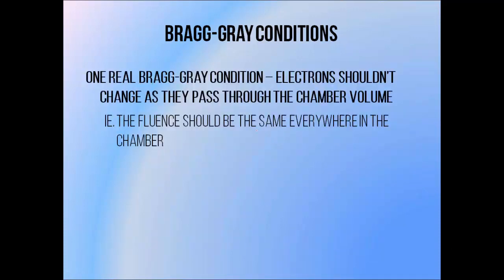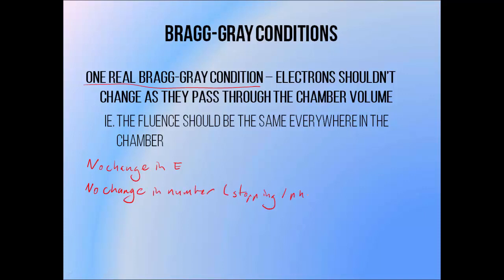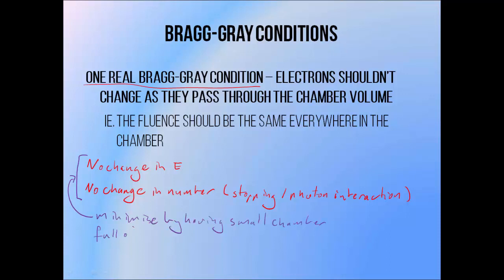All of these conditions can really be grouped into one: that electrons shouldn't change as they pass through the chamber volume. That means they shouldn't change energy, and there shouldn't be any change in number due to stopping or due to photon interactions. In MeV beams, ionisation chambers fit these conditions fairly well by having small volumes filled with air, which has an extremely low density, so it doesn't take much energy from electrons as they pass through, and in MeV beams it doesn't absorb many photons either.